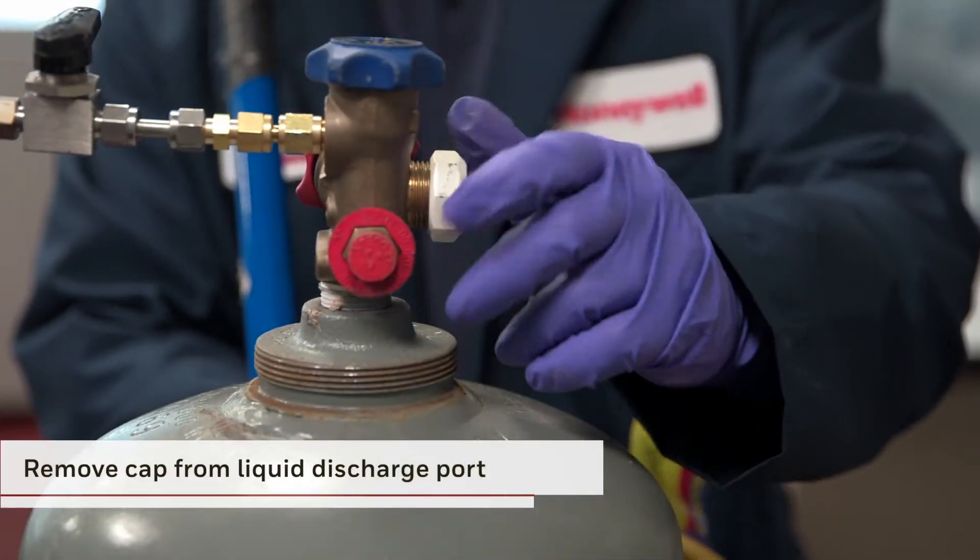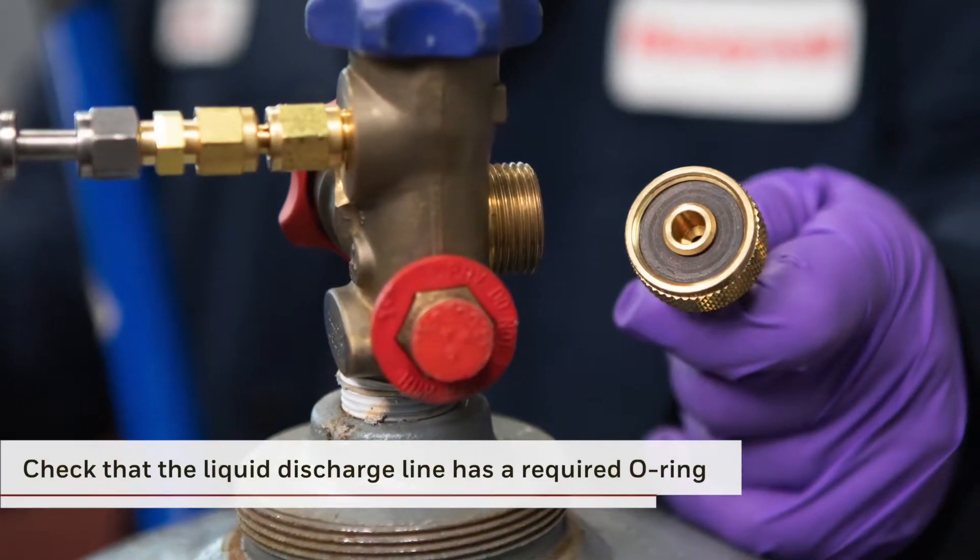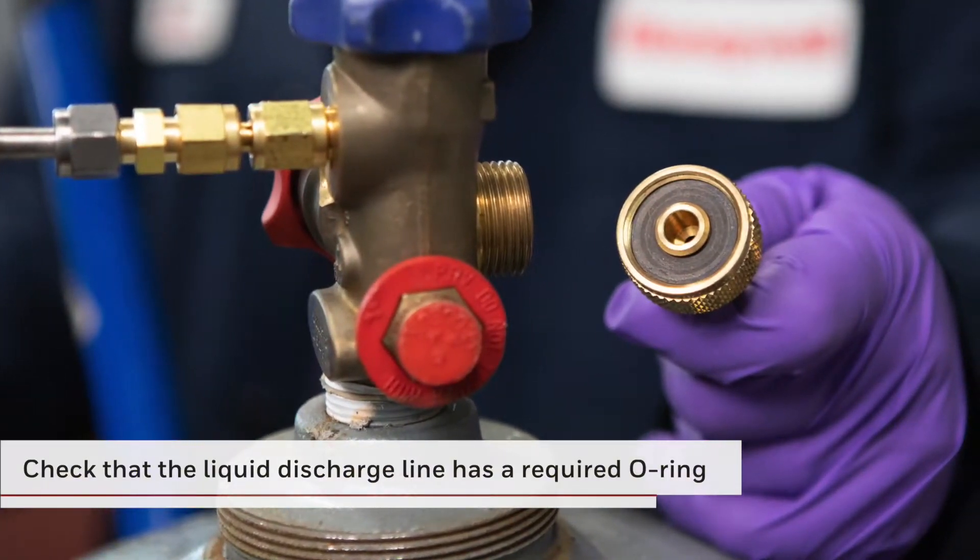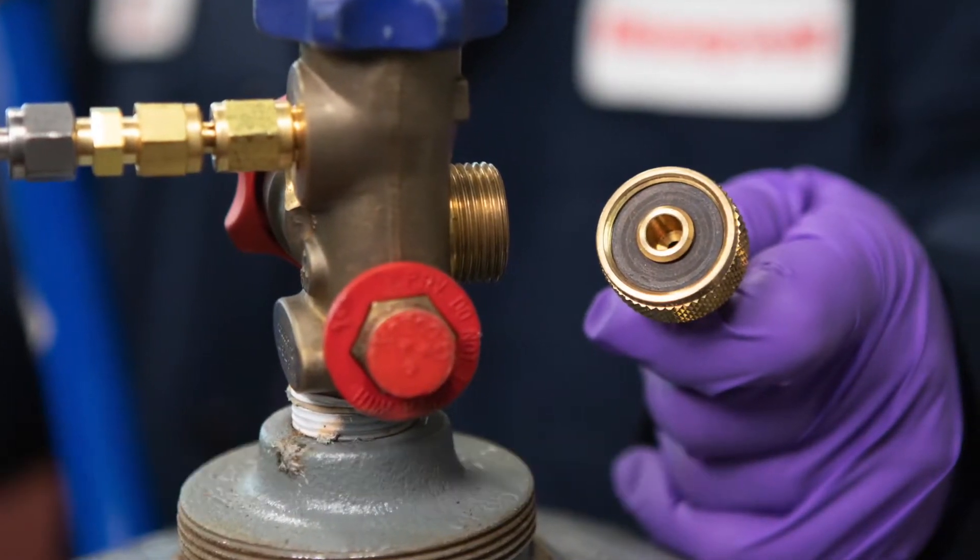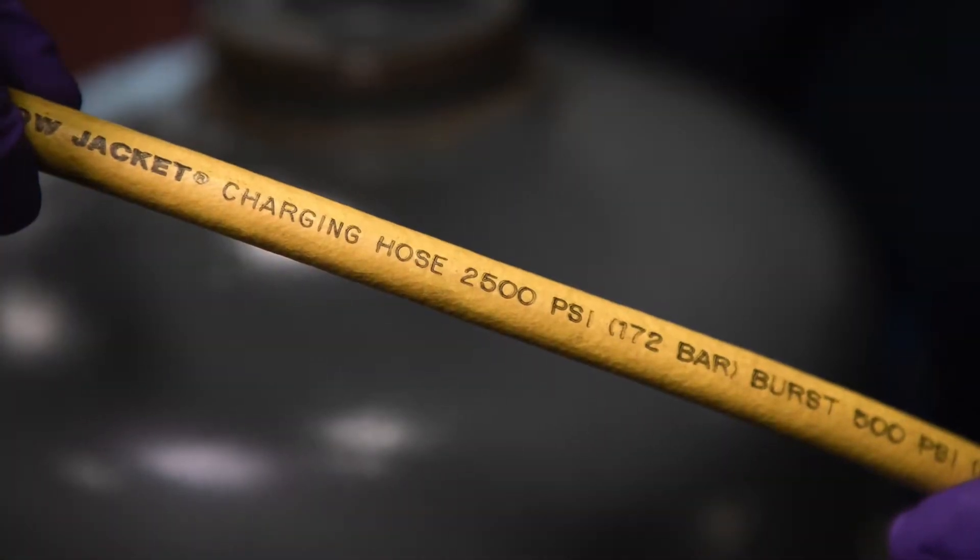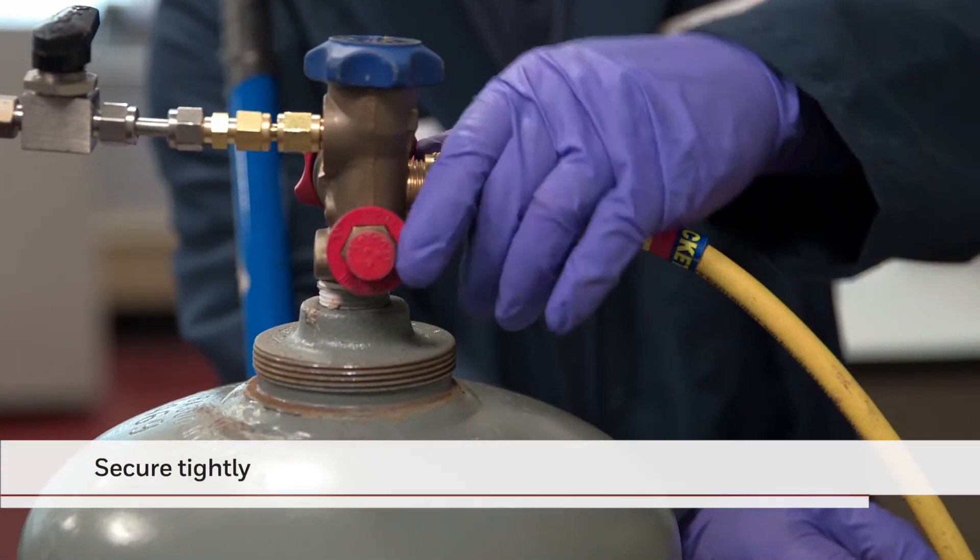Next, remove the cap from the liquid discharge port on the blowing agent cylinder. Before attaching the liquid discharge line to the large port on the blowing agent cylinder, make sure to check for the required o-ring. It is also critical to ensure that the line is rated for the desired pressure and the hose material is compatible with the blowing agent. Connect the liquid discharge line and secure tightly.